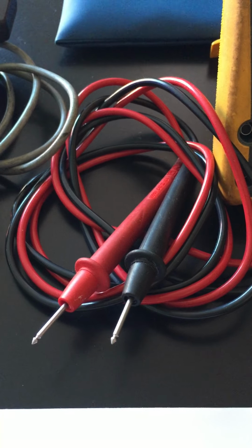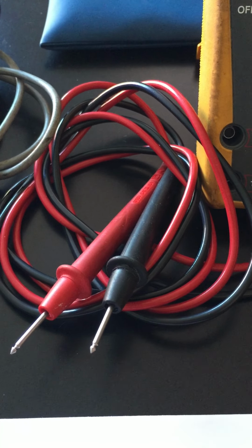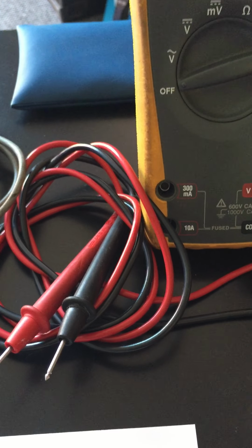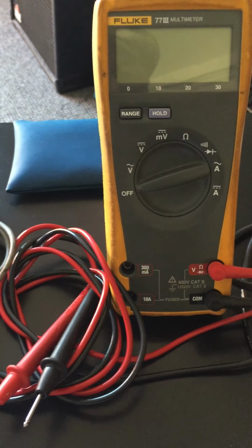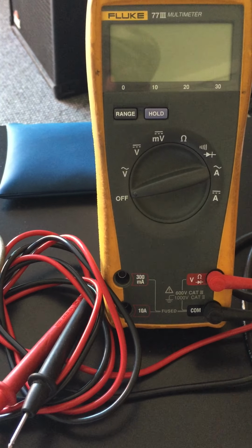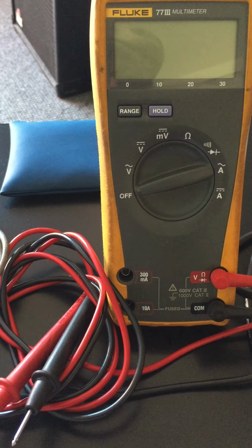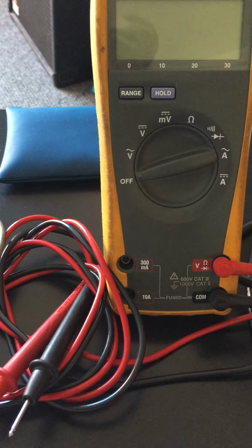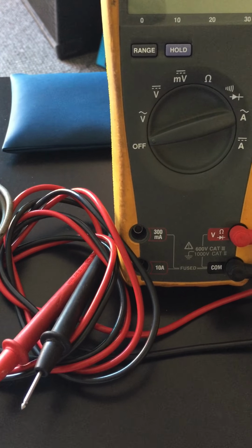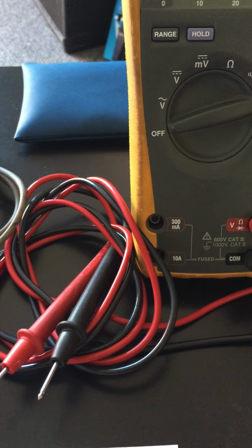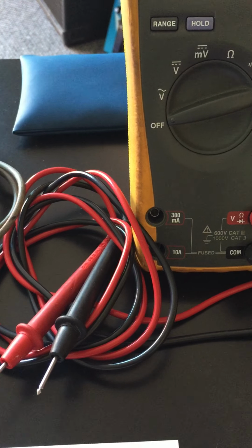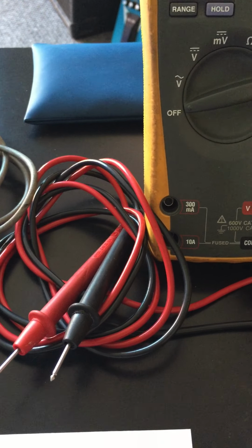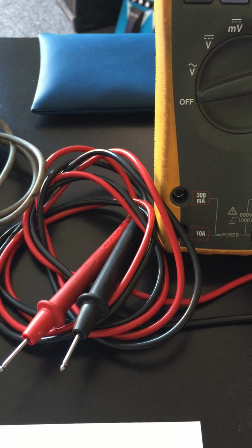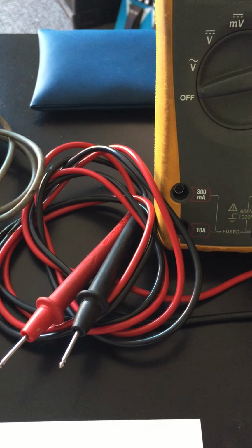Now, a multimeter. You might say, well, based on what you just said, no, but it depends what you're going to use them for, because, like I say, if you're testing on equipment or circuits where the voltage levels are lower than 50 volts AC or 120 volts DC, it's not a problem. Likes of that meter, if we were using the low resistance ohm function, not a problem. And I wouldn't be surprised if somewhere in the manufacturer's instructions it says, well, these are the leads that come with the instrument. If you want to carry out testing above those levels that I've mentioned, you really ought to have GS38 approved leads. I don't know that for sure, but anyway, it'll be a sensible thing to say.